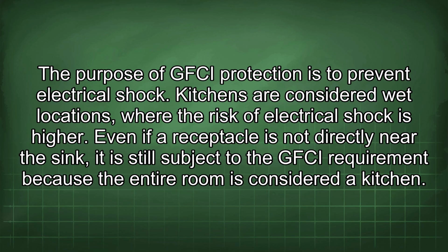The purpose of GFCI protection is to prevent electrical shock. Kitchens are considered wet locations, where the risk of electrical shock is higher. Even if a receptacle is not directly near the sink, it is still subject to the GFCI requirement because the entire room is considered a kitchen.